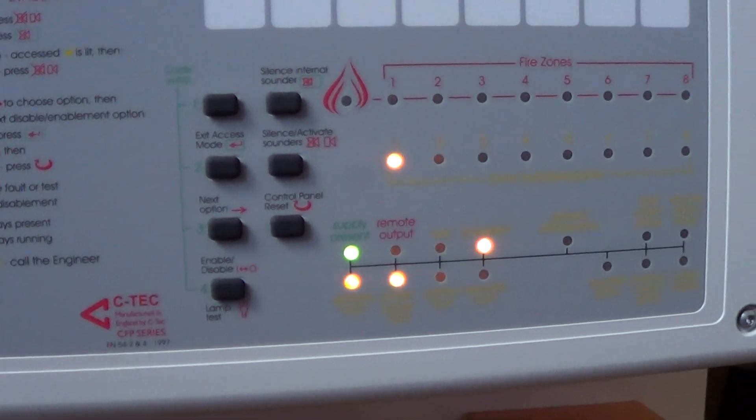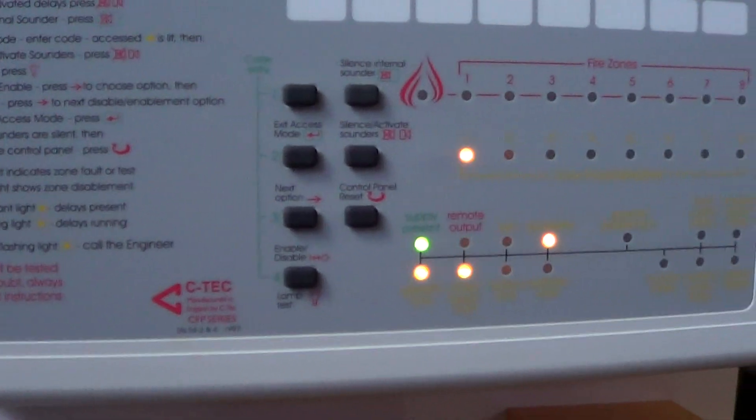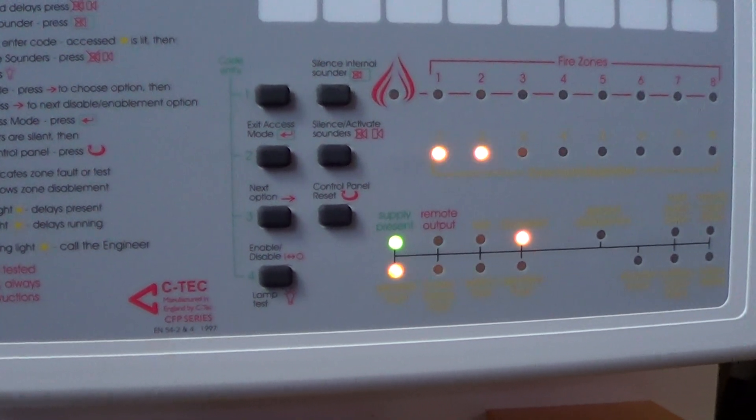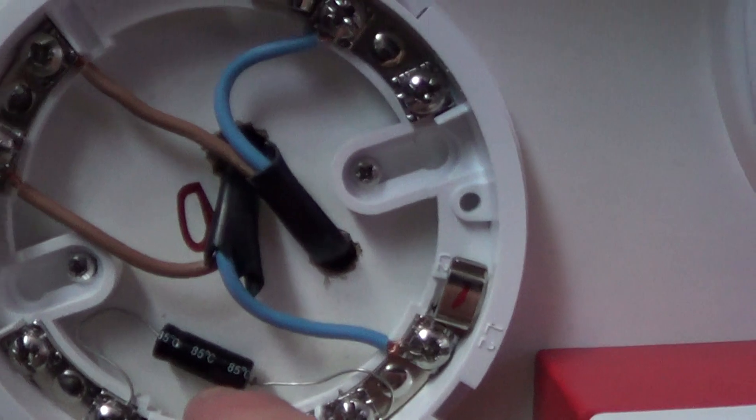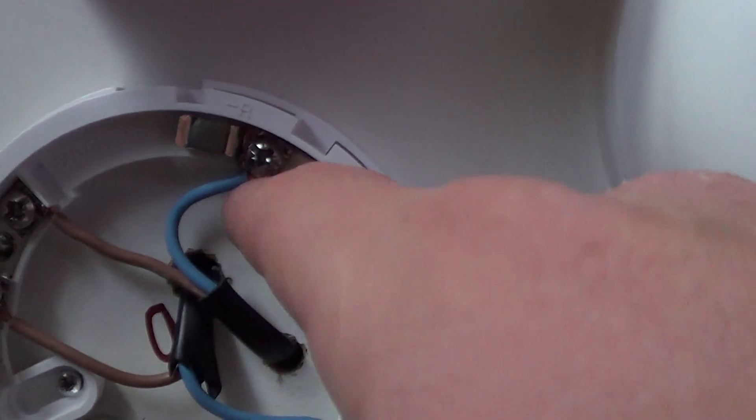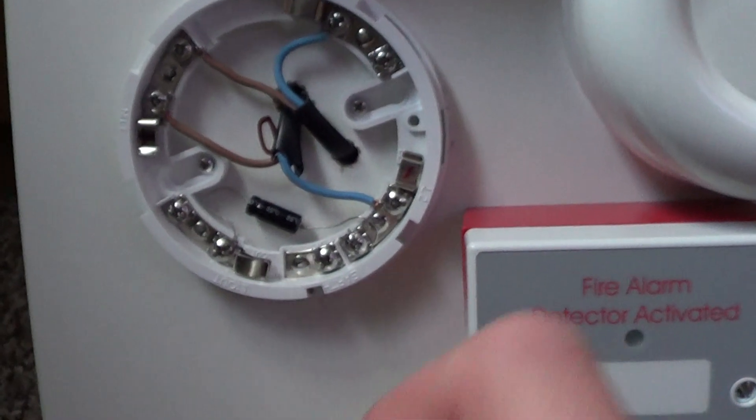The fault light will come on in a minute. Try reset the panel, see if that makes it quicker. See, there we are. This is the wiring in the detector head. This is the end of line resistor, this is the zone wiring here, positive and negative, and this is the remote output indicator here which the smoke detector turns on.